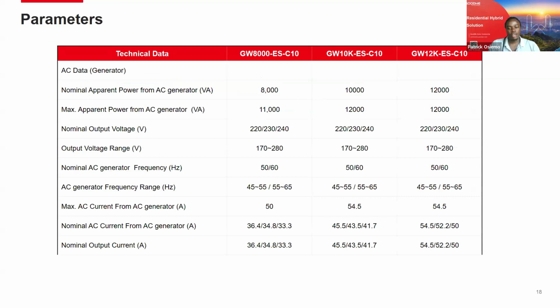Now on the AC part, I mentioned that we're able to connect to a generator AC. It depends on the inverter rating. If we have the 8 kilowatt, you're able to connect an 11 kVA single phase generator. And for the 12 kilowatt inverter, you can connect a 12 kVA generator. Because generators, in terms of age, might output voltage that is not that stable, similar to the frequency, this port can be configured to take in voltage as low as 170 to as high as 280 volts. For the frequency, as low as 45 hertz to as high as 55 hertz.